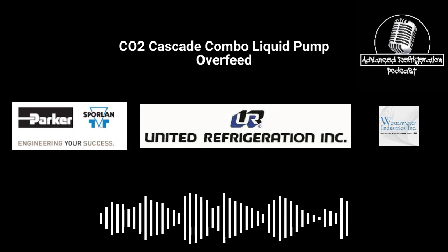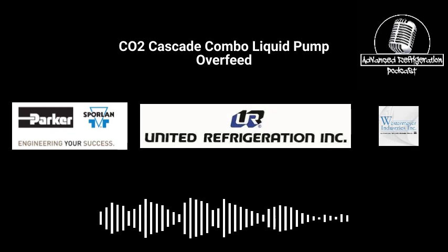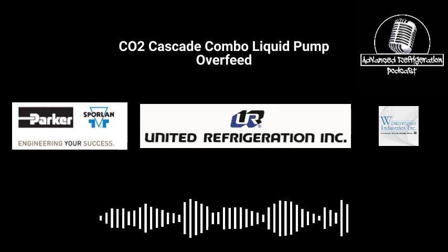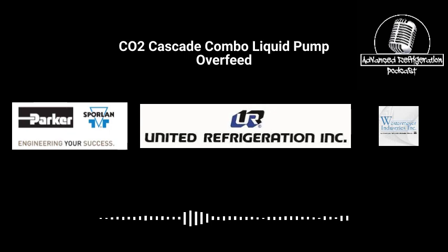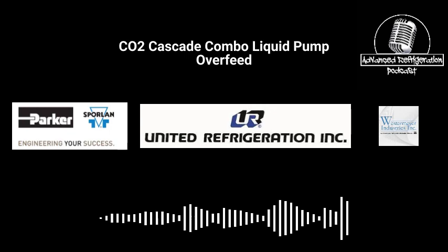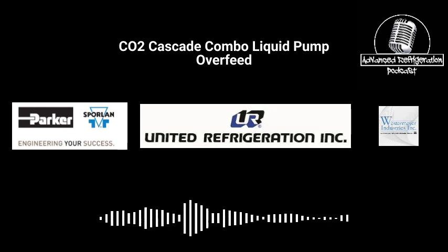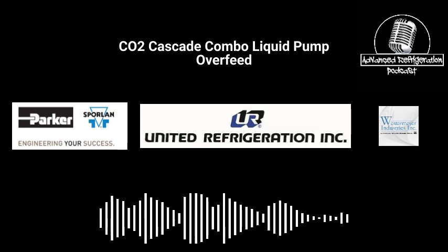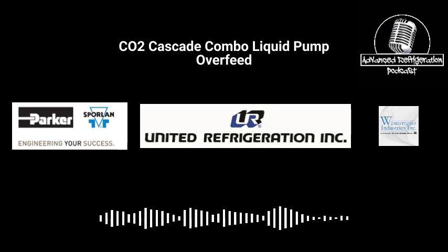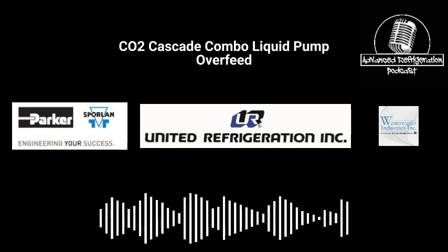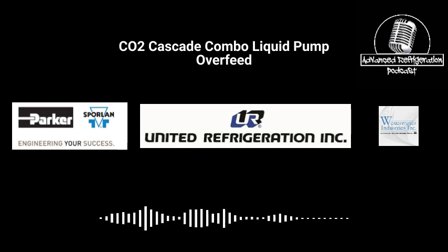Like I said, it's comparable to having a K body, because those are air cooled compressors. That's why it's always sitting in front of a condenser fan, right? So dumb. You'd think they would just not put that in there like that. It's just one more thing for somebody to mess up. Yeah, I know. They should just always make it be a suction gas. I don't know. There's got to be a reason why they're doing it.